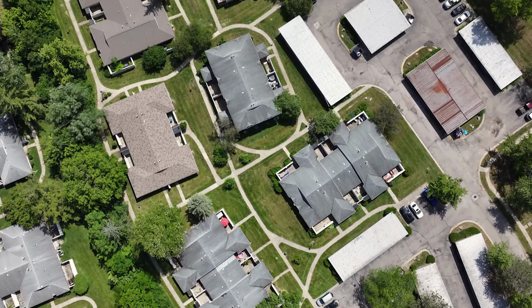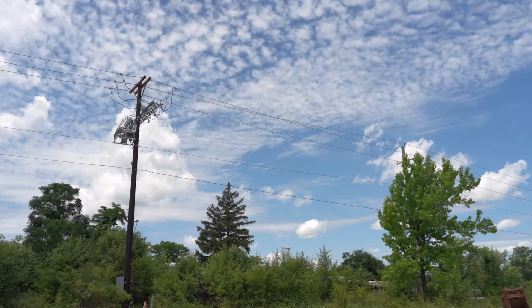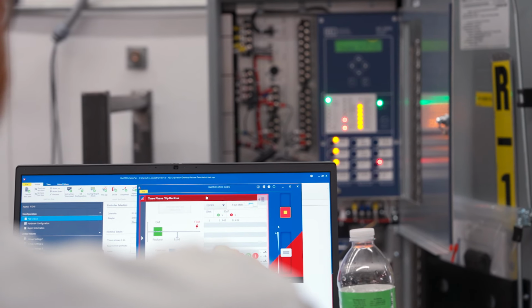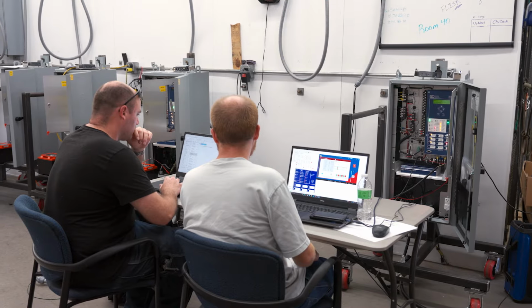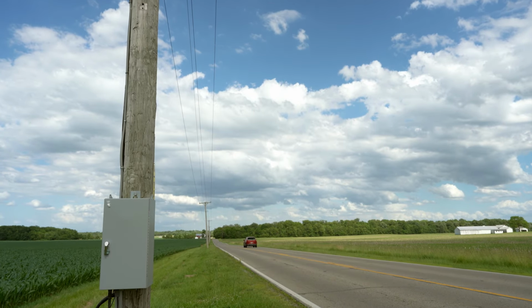We decided to have a big initiative to start applying a numerous amount of smart grid reclosers over a 6 to 10 year period. If we have a distribution circuit that we're a third of the way out, you have a fault and you have 4 reclosers on it, and maybe the second one is opened up and you've now stranded 2 sections beyond that. So now we can restore those from another source automatically. We're typically putting up somewhere between 70 and 100 smart grid reclosers per year.